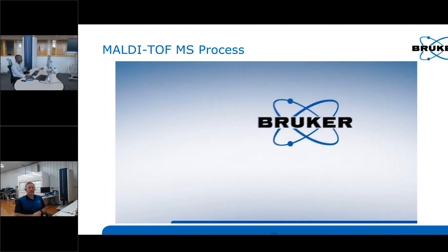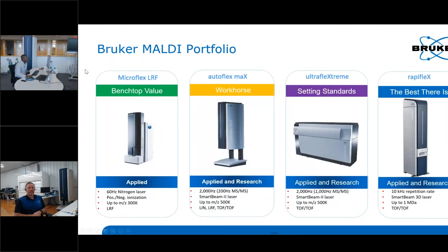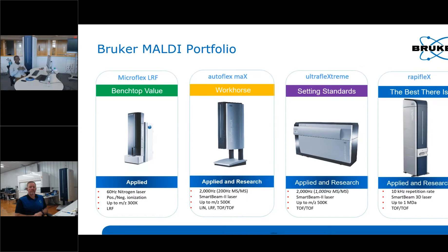That paints a picture of what's going on inside the instrument as we analyze samples. At Bruker we have three levels of MALDI instrumentation, and instrument choice depends on the type of application needed. On the lower end is the Microflex LRF, a benchtop system that's a good option for simple MALDI experiments — fast and easy QC of synthetic peptides, polymers, oligonucleotides, and all types of samples.